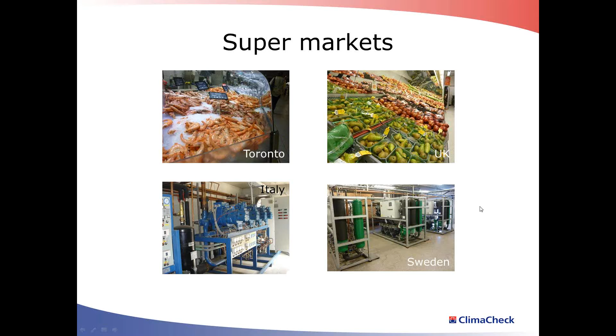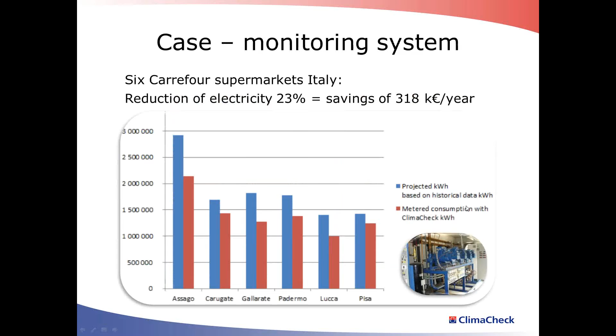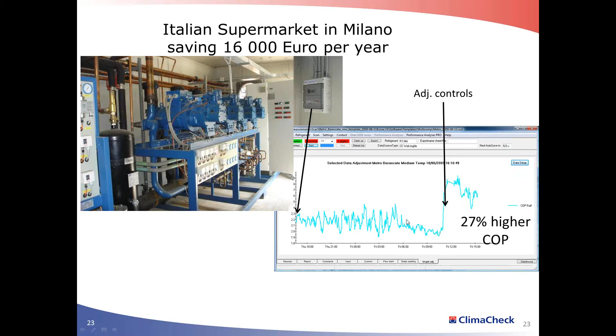So, as I mentioned, the supermarket is another sector where we measure on many systems around the world, both the traditional ones and then to the right is actually a supercritical CO2 system, which is the latest development in supermarket refrigeration. And this case is a supermarket in Italy, where they measured over one night when they mounted a fixed installation, and then they could adjust the control settings, and they could improve the COP by 27%.